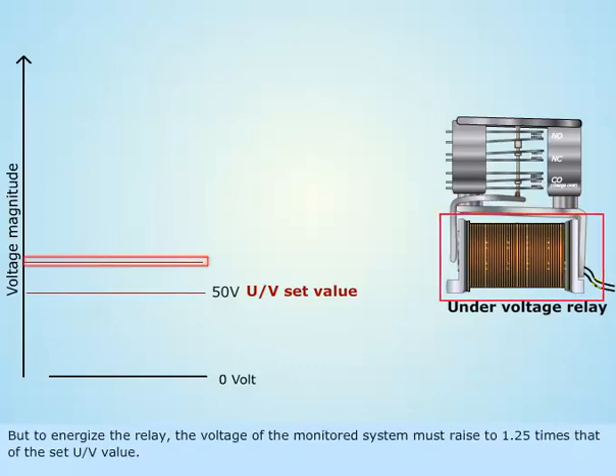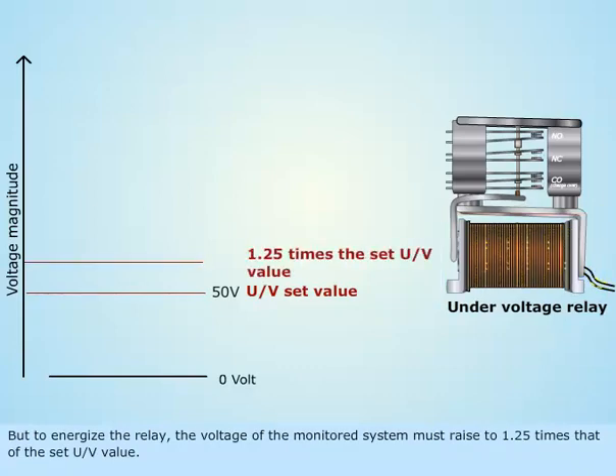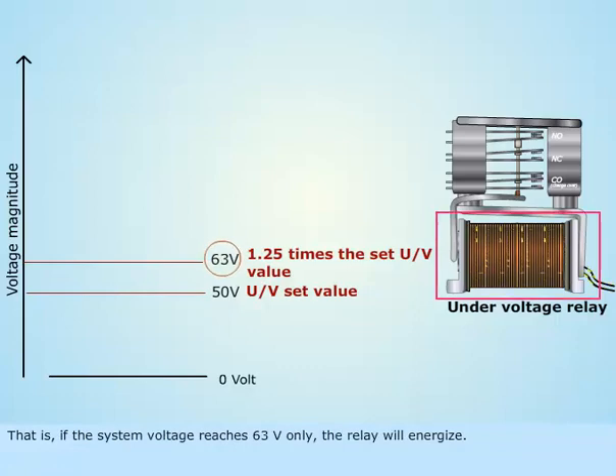But to energize the relay, the voltage of the monitored system must raise to 1.25 times that of the set under voltage value. That is, if the system voltage reaches 63 volts, the relay will energize.